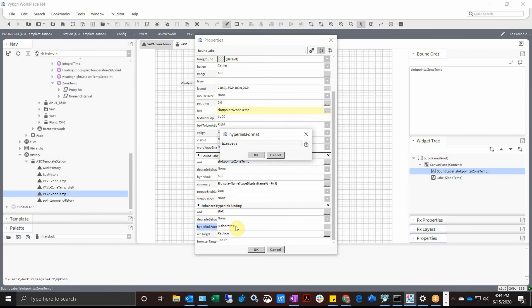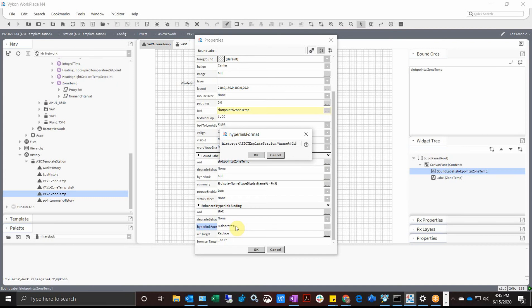Colon forward slash and the name of the jace or the station basic template station, and it is important you get that right. And then forward slash, and then you do something like percent name. And then mine you notice has a dash in it, so the representative for a dash is of course dollar sign 2d, and then I can put zone temp.